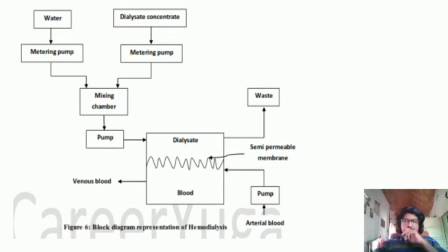So naturally one question will arise, what exactly is happening inside the dialyzer? The core of the dialyzer is made up of thousands of tiny mesh tubes, just like in our kidney. The blood flows inside each tube, and the dialysate stays on the outside of the tube. The blood passes through the tiny mesh of the tube, and the dialysate stays outside of the tube. These tiny pores in the tube let the waste and excess fluids pass from your blood into the dialysate.